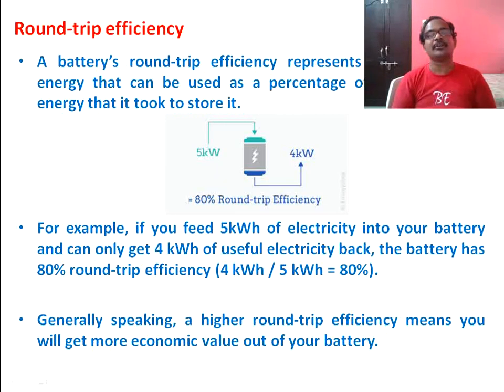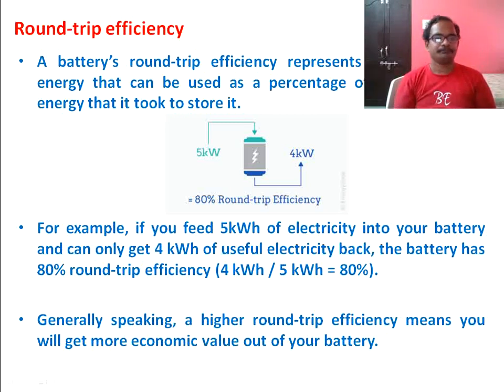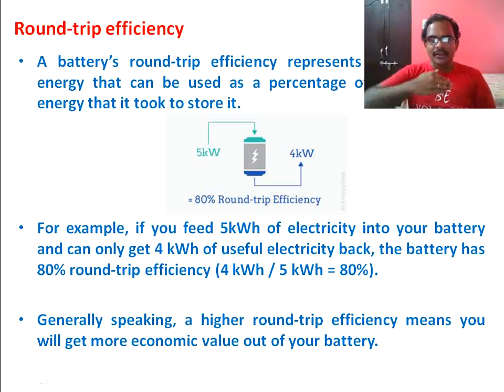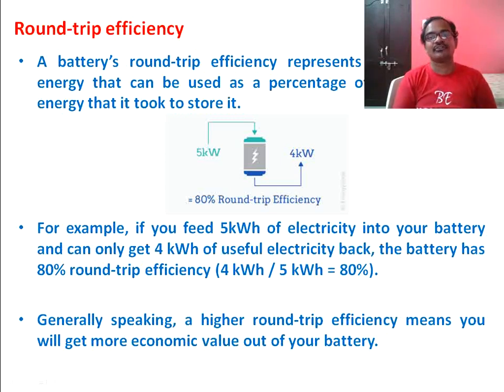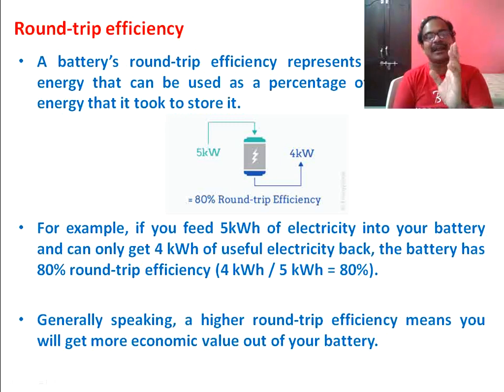The next point is round-trip efficiency — the efficiency of a battery through charging and discharging. For example, if you feed 5 kWh of electricity into the battery but can only discharge 4 kWh from it, then 1 kWh is lost in the charging and discharging process. The round-trip efficiency is 4 divided by 5, which is 80%. This round-trip efficiency should be as high as possible.